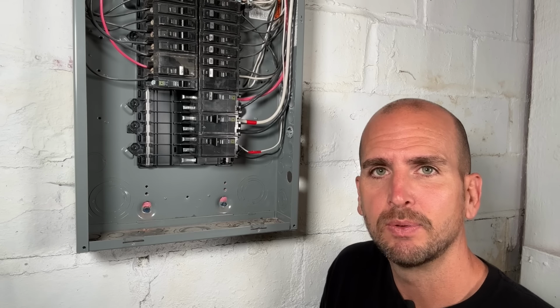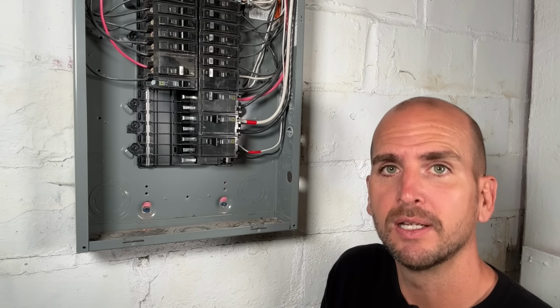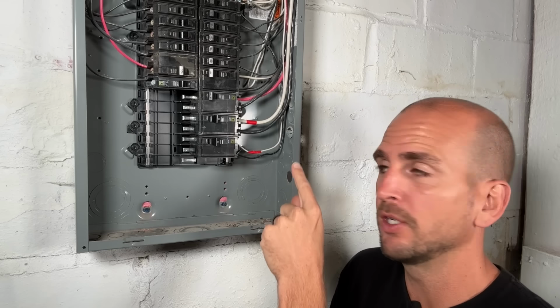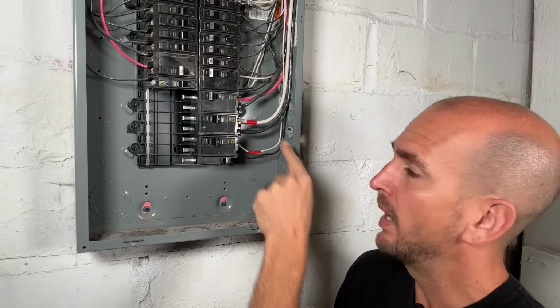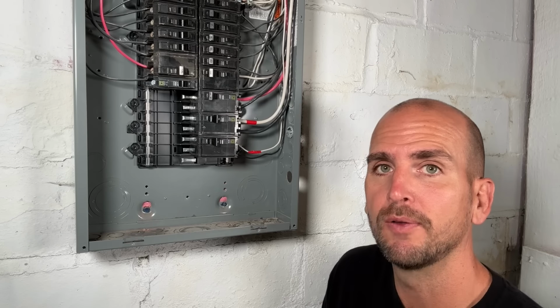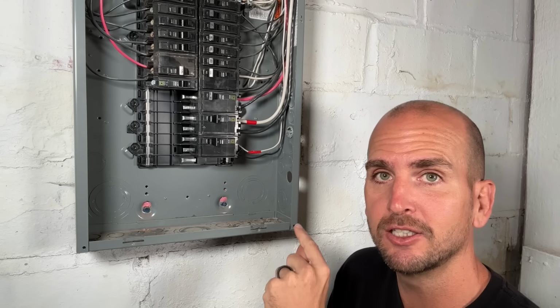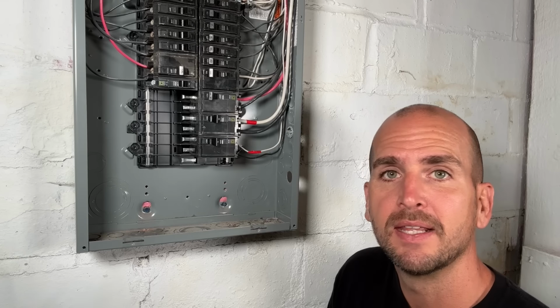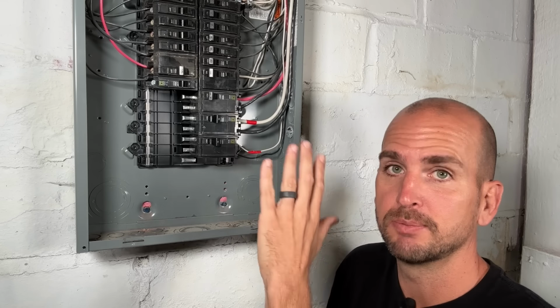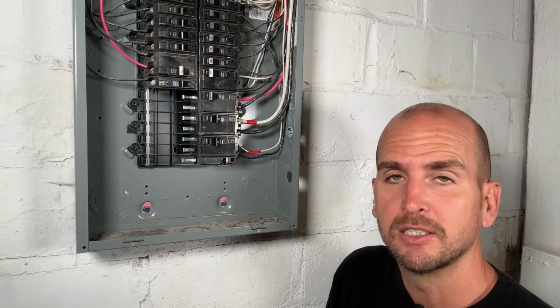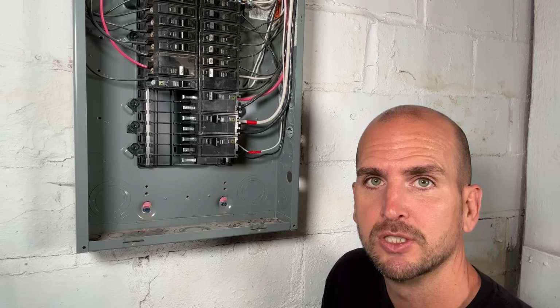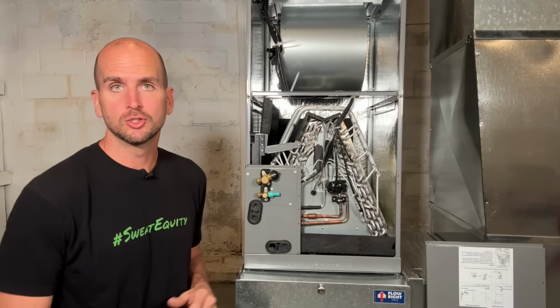I called this out in one of my other videos, but I did not mark it, and that was a mistake. So make sure you mark those to indicate, okay, this white wire here is no longer a neutral. It is actually serving as a hot conductor in this application. And then that's gonna help out anybody in the future just make sense of this wiring and easily service the system or make changes. Now moving on to installing a drain line.